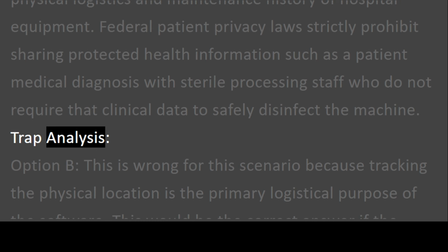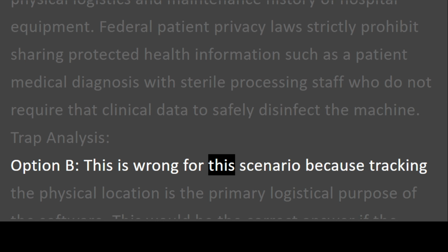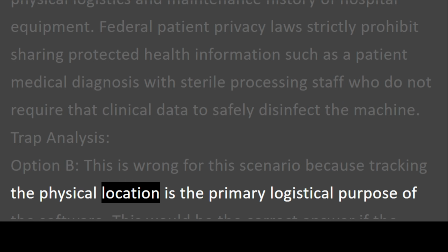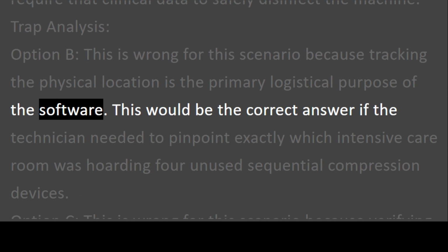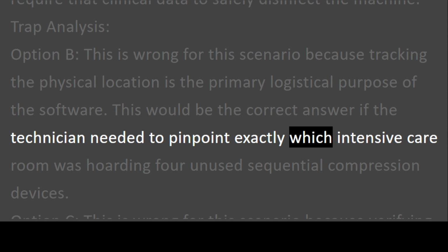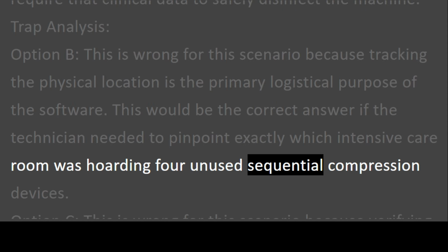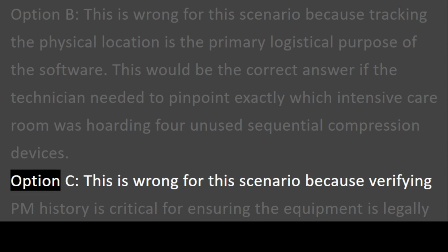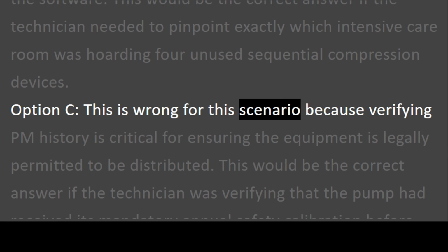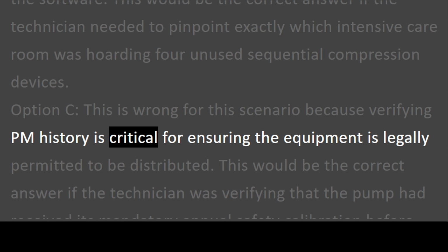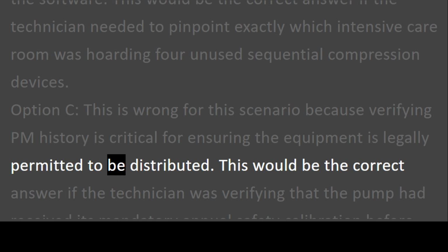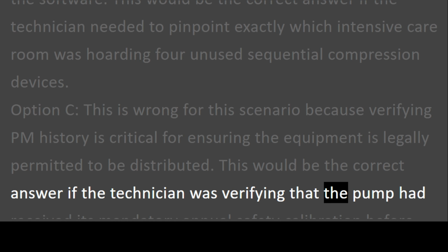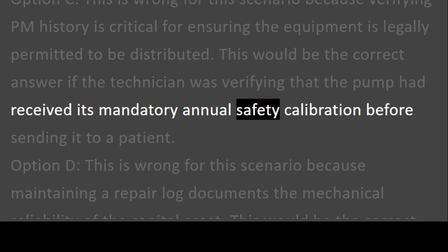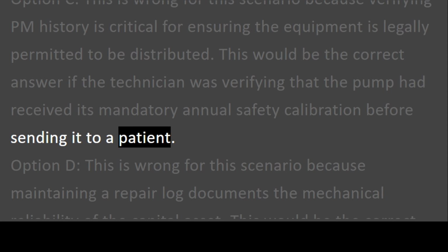Trap analysis. Option B. This is wrong for this scenario because tracking the physical location is the primary logistical purpose of the software. This would be the correct answer if the technician needed to pinpoint exactly which intensive care room was hoarding four unused sequential compression devices. Option C. This is wrong for this scenario because verifying PM history is critical for ensuring the equipment is legally permitted to be distributed. This would be the correct answer if the technician was verifying that the pump had received its mandatory annual safety calibration before sending it to a patient.